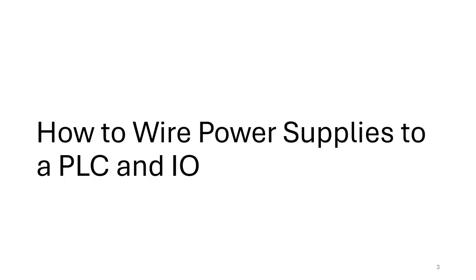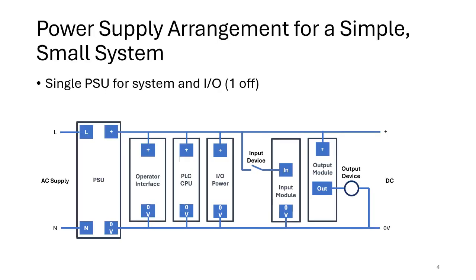So let's look at how to wire power supplies to the PLC and to the I/O devices. The easiest arrangement is a single power supply, which is appropriate for a simple small system. We have the incoming AC supply on the left hand side. That goes through the power supply and it's converted into the lower level DC voltage that we use for the system itself, typically 24 volt DC. We would use that same voltage to provide power to all the components.